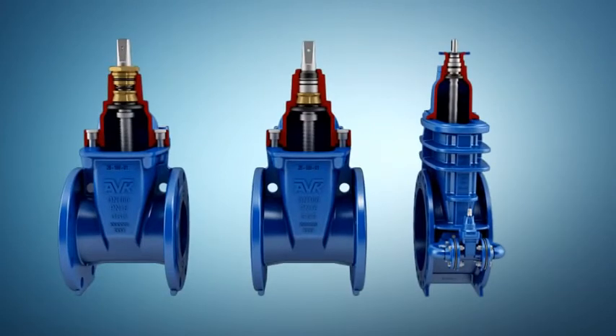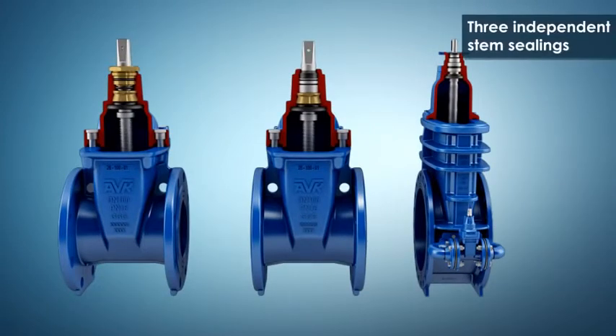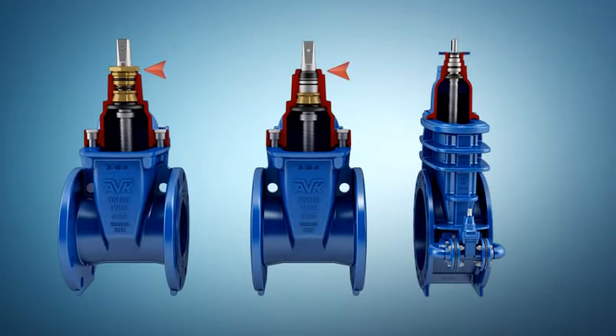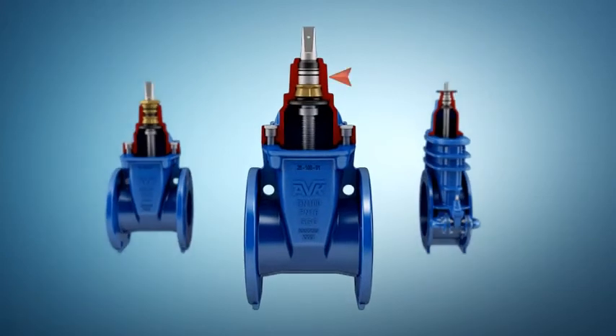AVK offers three independent sealings. A wiper ring seals against impurities from outside. NBR O-rings provide tightness around the stem. A rubber manchet or O-ring is the main sealing against the flow. The polyamide bearing prevents corrosion.